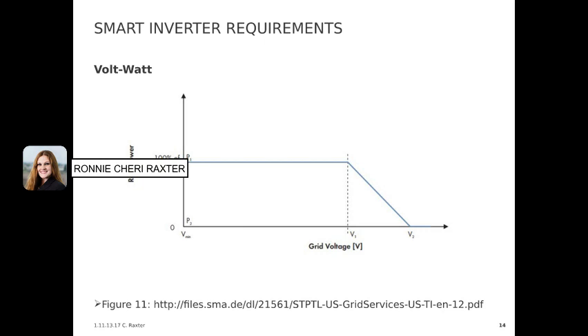The next functionality, which is actually the last one, is the volt-watt functionality. Similar to the last one we discussed, it is optional. It typically comes deactivated. This functionality would reduce the power output of the connected DER inverter if the grid voltage is high. And the reasoning, as we discussed before, is high voltage is associated with high DER penetration. So having the DER inverter reduce the power output would reduce how much voltage was being raised due to high DER penetration. And although this functionality could help stabilize the grid, it could also potentially mask high consumption areas. And without monitoring in place yet, that could potentially prevent the utility from knowing if their feeders were in need of upgrade.